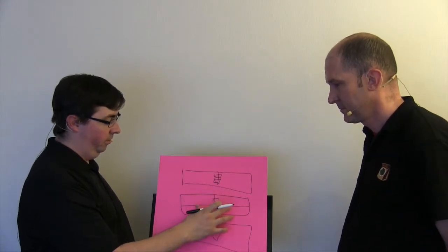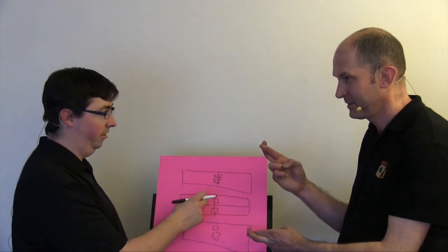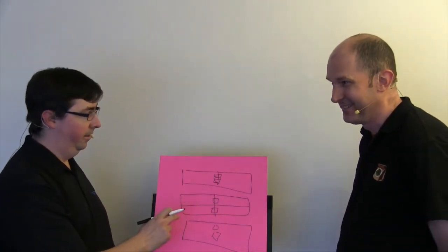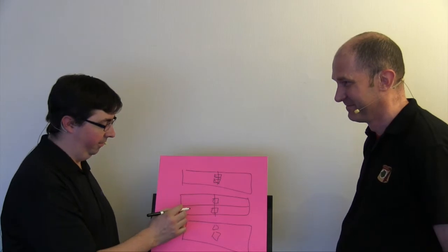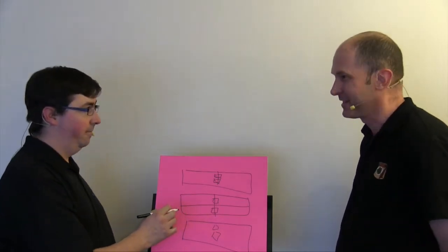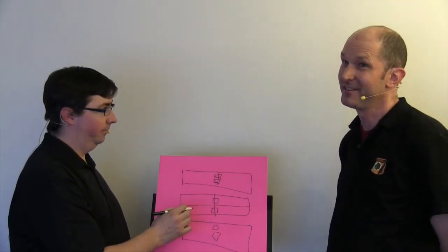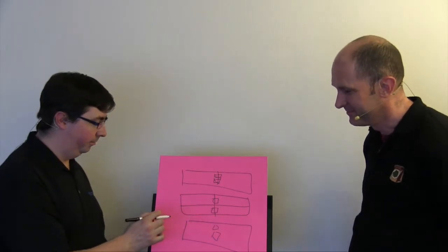The power is shared, but in your rack you will have 2 completely independent power feeds, A feed and B feed. I hope so. You hope so, absolutely. Better test that. Yep. Yeah, absolutely better test that. I have seen situations where racks have gone down because I talked to people last week who had exactly that. Yep. They thought they had A and B, but some devices were both on A. Yes, so that's not a good scenario.